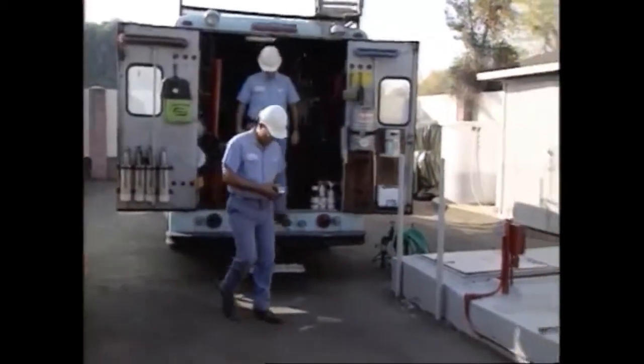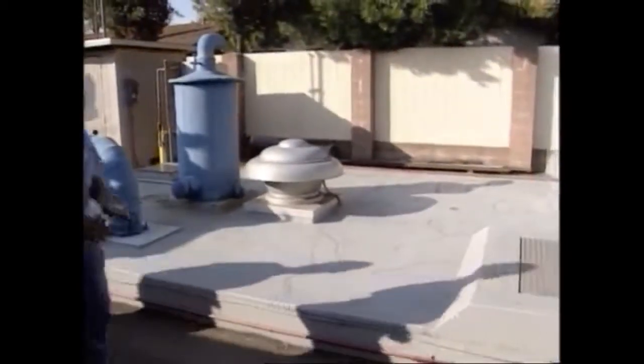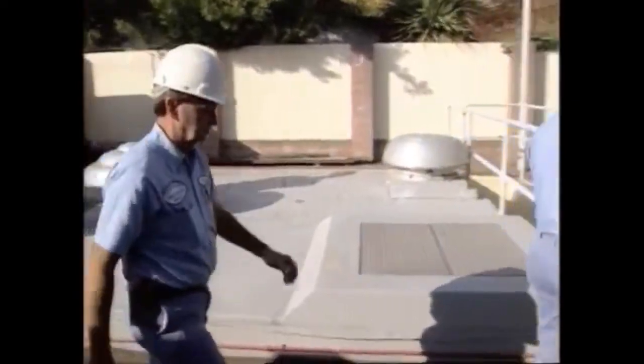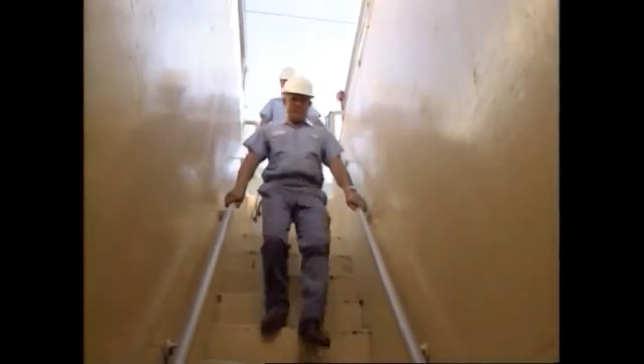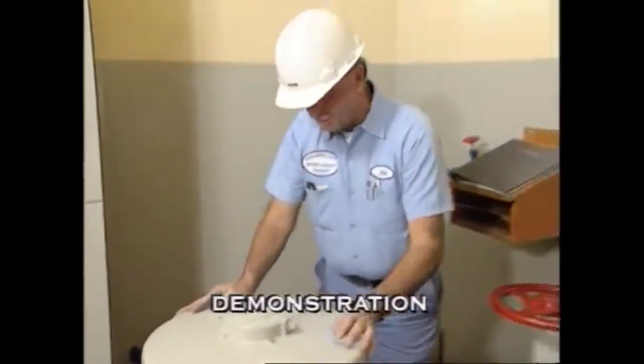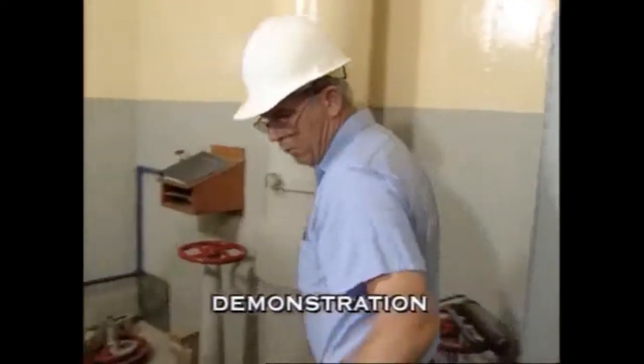Lift stations can be operated automatically, and if designed and maintained properly, do not require daily visits. The truth is, daily visits cause some operators to let a station get by on a quick glance because they were there yesterday and will be back tomorrow. Stations that are visited daily may be dirtier and more in need of maintenance than stations visited less frequently. Important maintenance items are often delayed until tomorrow, which sometimes doesn't come for a month. It's okay. We'll check them tomorrow.